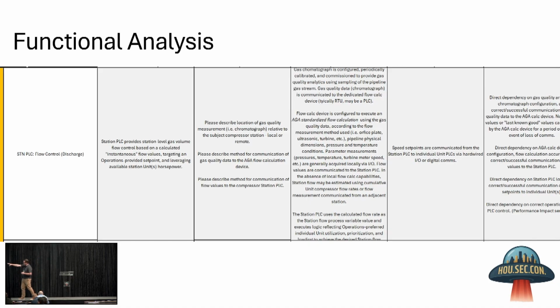But as those inputs are delivered, what are the actual computations that occur? Because that computation, where does it often sit? That computation exists within the PLC controller, or within a SCADA server, or maybe within a DCS solution. Understanding where that calculation exists and what's involved in it helps us identify opportunities where, as an engineer, we can think about increasing its resilience. Can I change the algorithm to be more resilient?